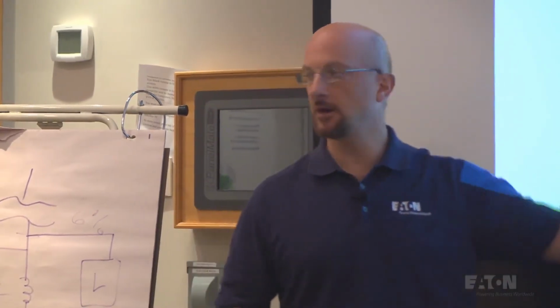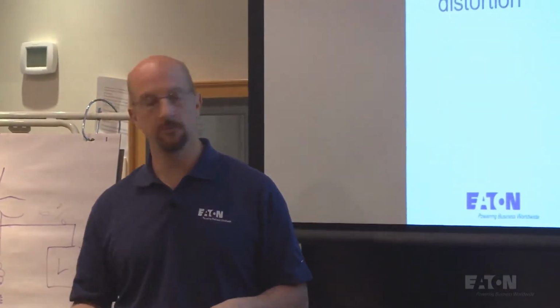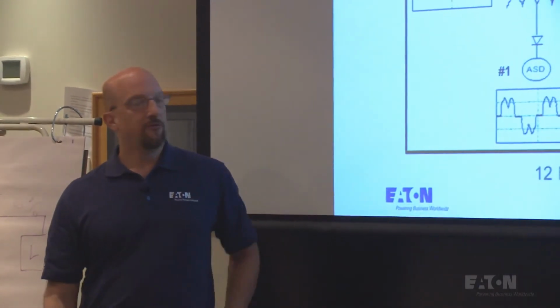If you have a fifth harmonic filter for a 6-pulse drive, that's common. The next one would be seventh. What if I have a 12-pulse drive? Where would my filter be? Just below the 11th. So I have to think about what my system looks like to decide where the filters need to be. How about phase shifting?